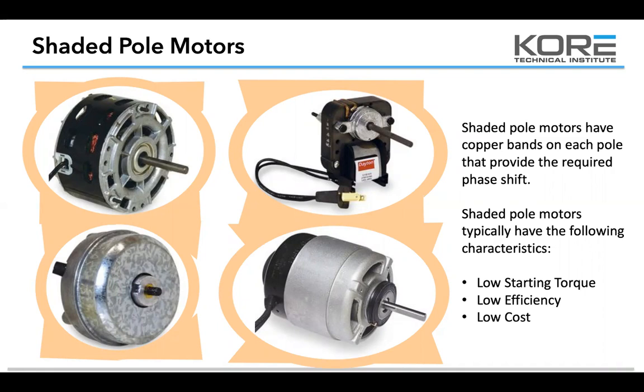Shaded pole motors typically have the following characteristics: they've got a low starting torque, low efficiency, and low cost. That's why you're usually only using these with a very thin fan blade on them. They're not meant to spin big blower wheels or squirrel cages. They can't handle a lot of load and don't have a lot of starting torque. If you do put a heavy load on there, it's going to take a little bit for that motor to get going. So this is where you're going to be looking at case fan blades or condenser fan motors. And if you're familiar with the field, you're looking at those going, yeah, I deal with those every day, all day. So it's a pretty typical motor we use in the trade.